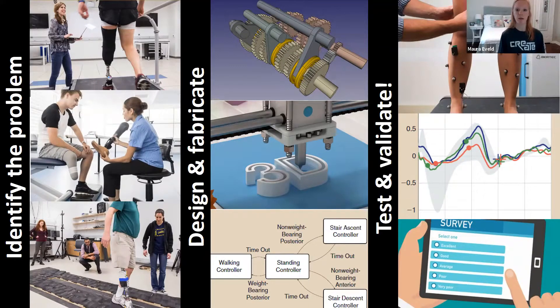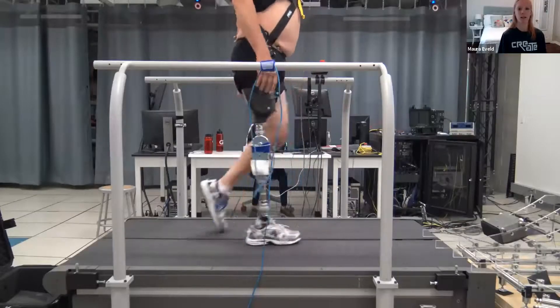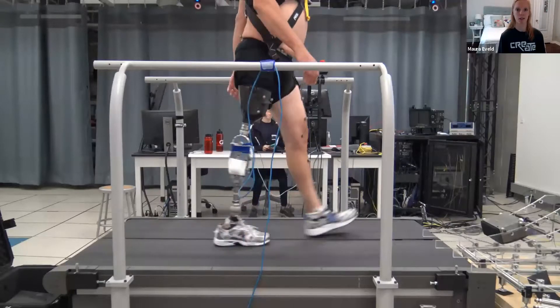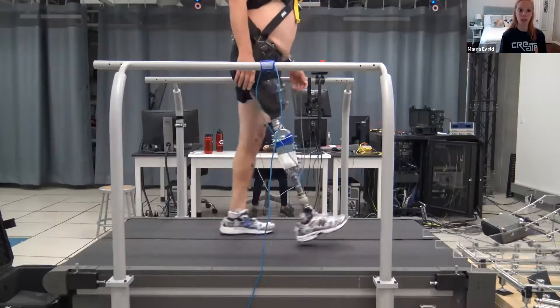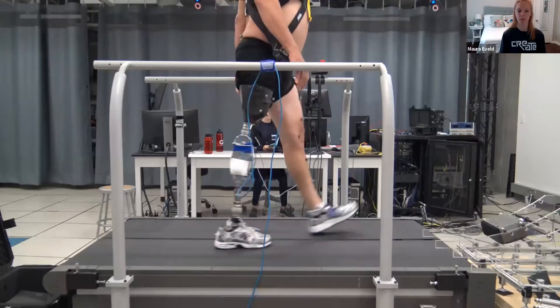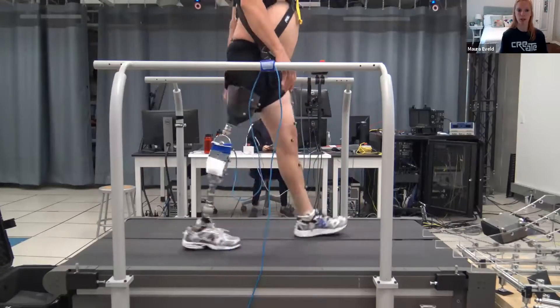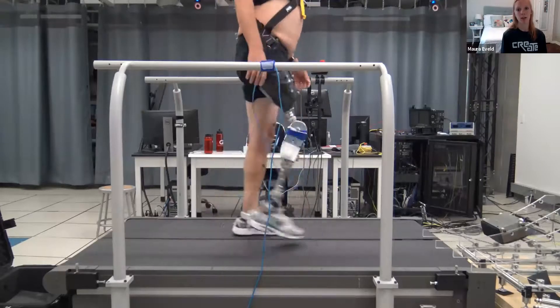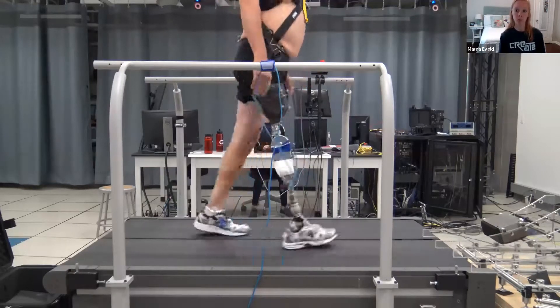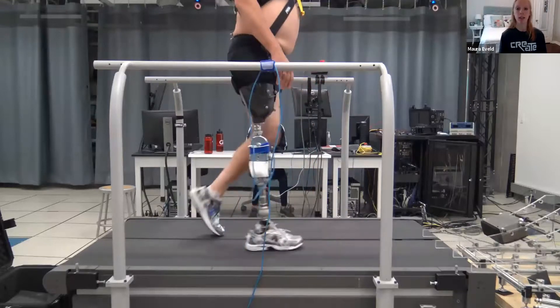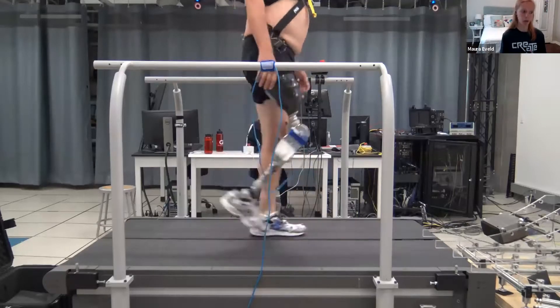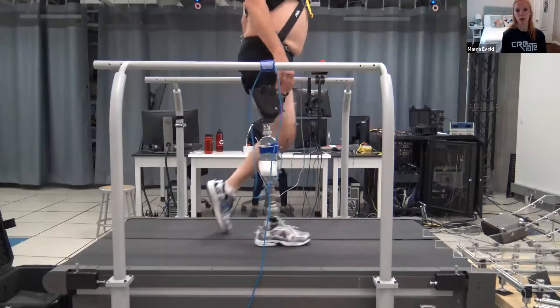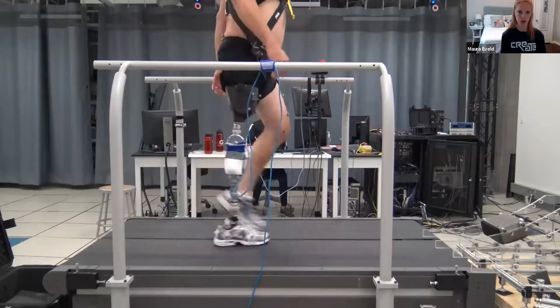Let me show you a few of the devices we've developed in lab in action. This first device is a lower limb prosthesis for individuals who have an amputation above the knee, so they need something that can replace both the knee and the ankle joint function. In this particular device, the knee joint is powered — it has a motor that allows the prosthetic knee to stay straight while the user bears weight on it, but also flex and extend when the other foot is on the ground. The ankle joint is unpowered or passive, acting more like a spring to help facilitate the landing and push-off of the foot during walking.